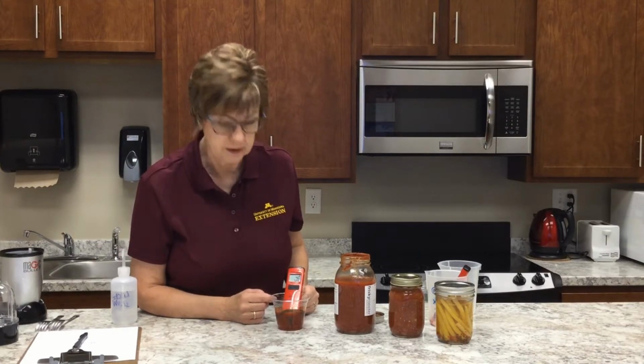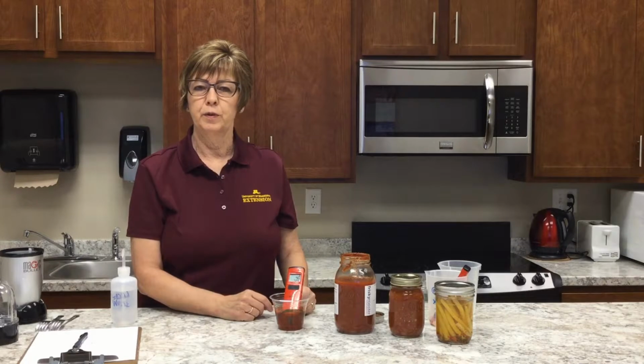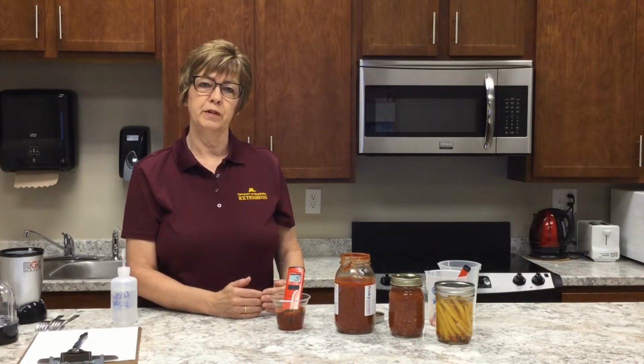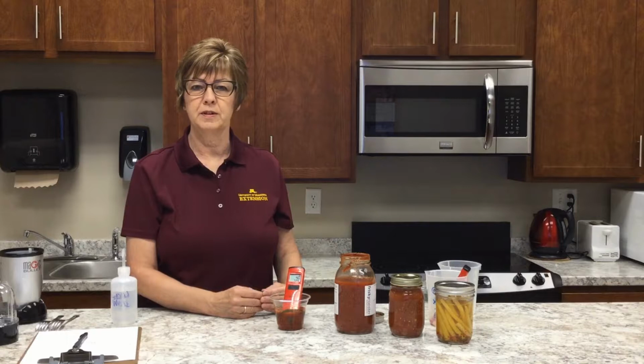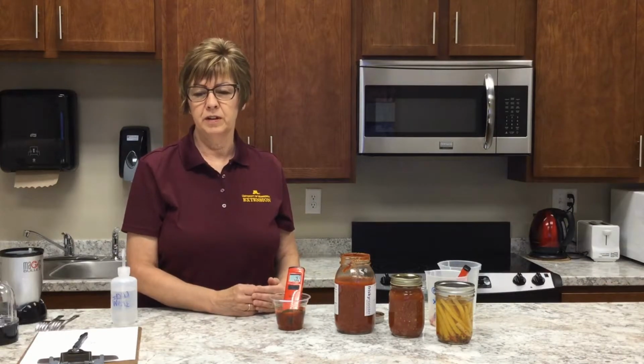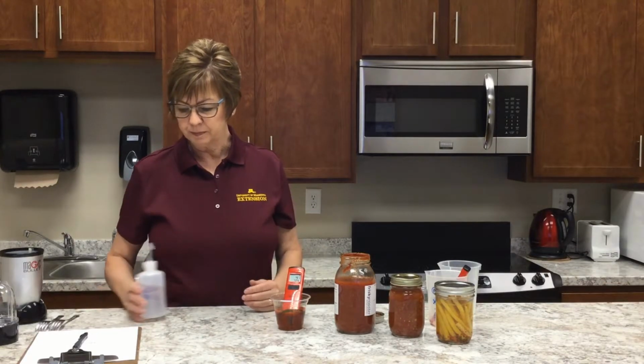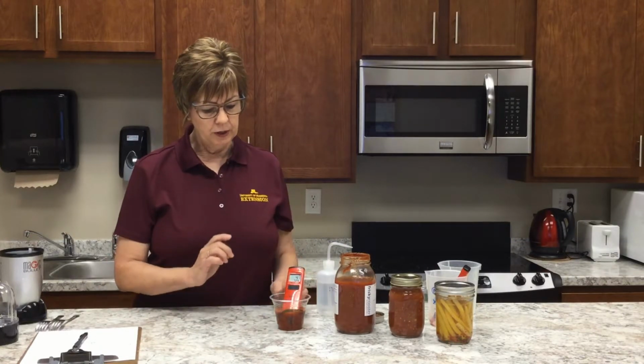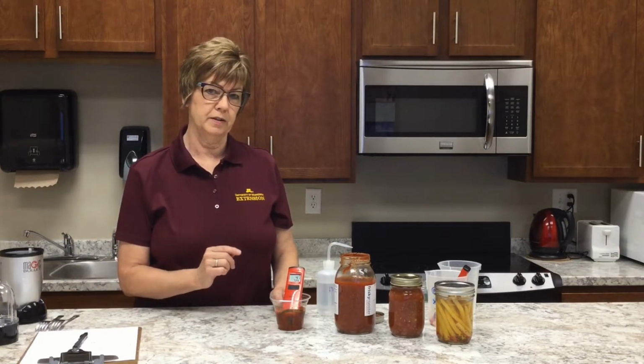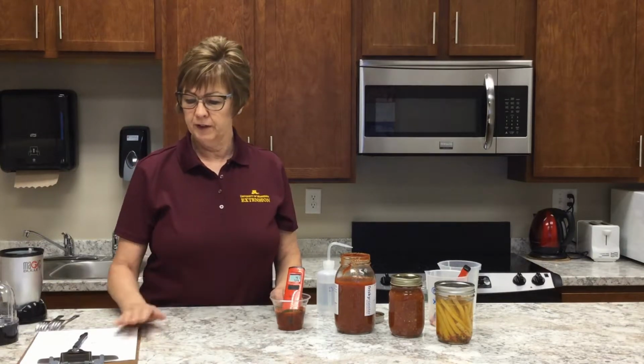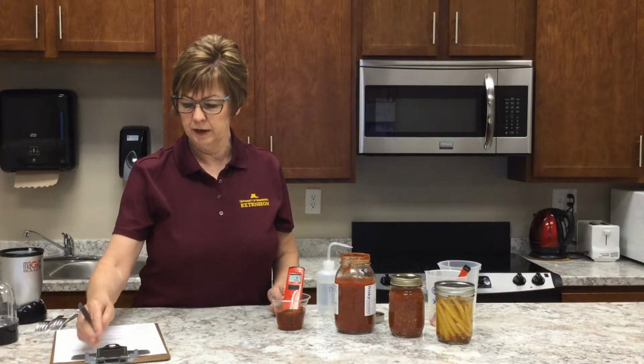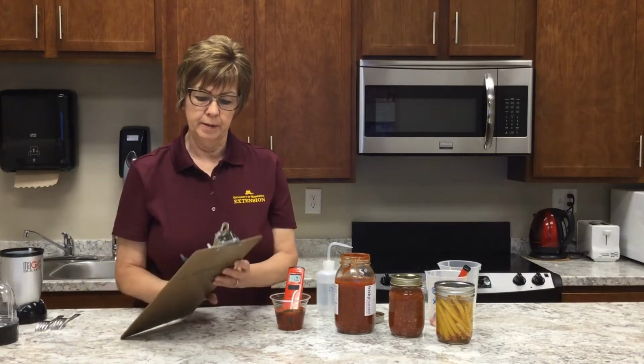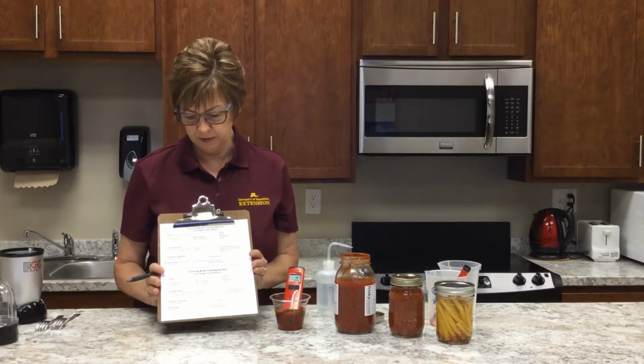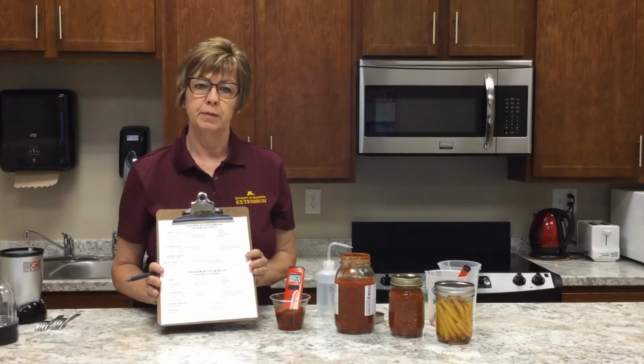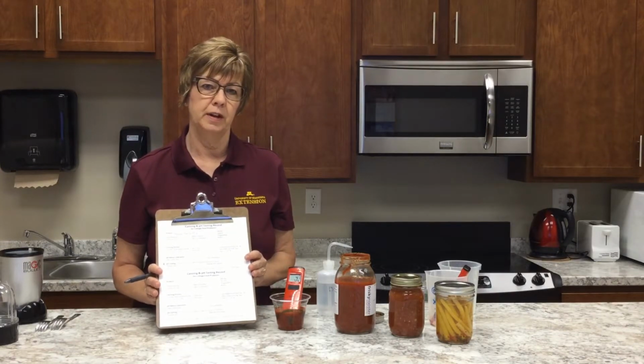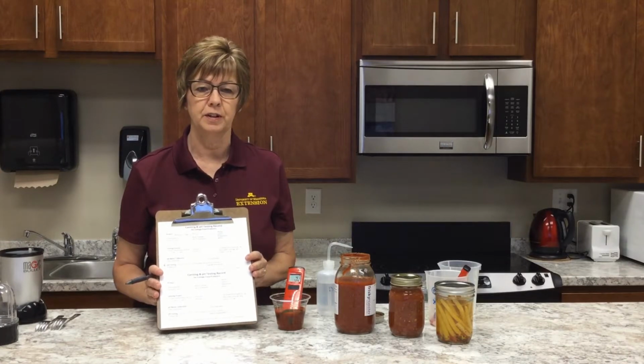And the result of this is 4.0. And so if we go back to that required level of equal to or less than 4.6, this product is within that measurement range. A couple things. We like to encourage you to do 2 tests per batch. And then a very important step is to actually record your results. And we do have a sample form that you can access in the resource section.